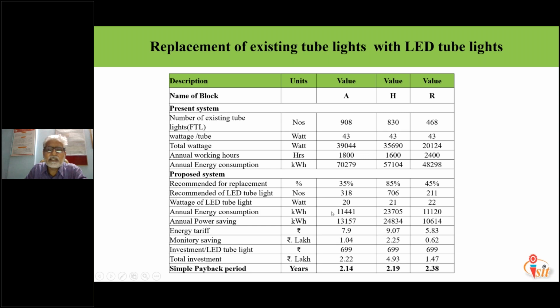So annual energy consumption for these 20 watt tube lights, 318 in number, for 1800 annual working hours, comes to 11,441 units for just these 318 tube lights. The annual power consumption saved compared to the 43 watt version comes to 13,157 units - this much electricity can be conserved by replacing the 43 watt tube light with the 20 watt one.